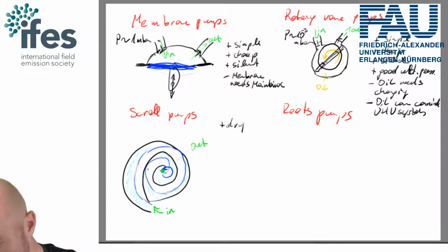Yeah, so usually those tips are made from PTFE, so you don't get the problem of any oil contaminating. So simple. I should put clean here as well. So they are dry. They are relatively silent, and they have a good pressure.